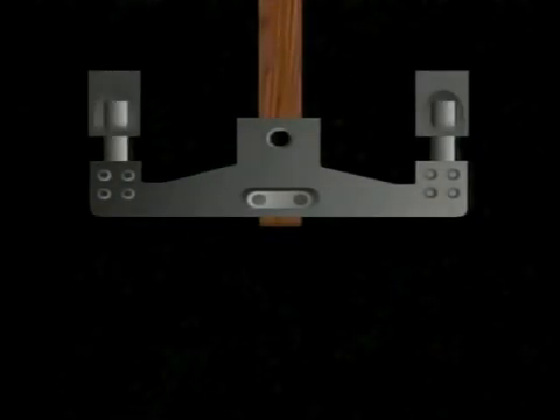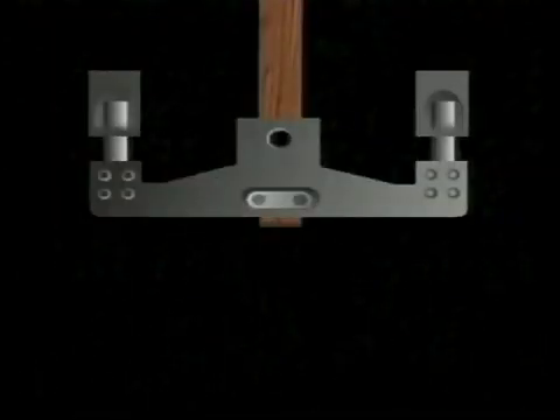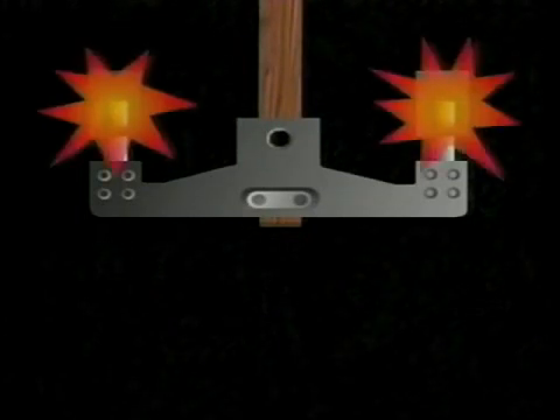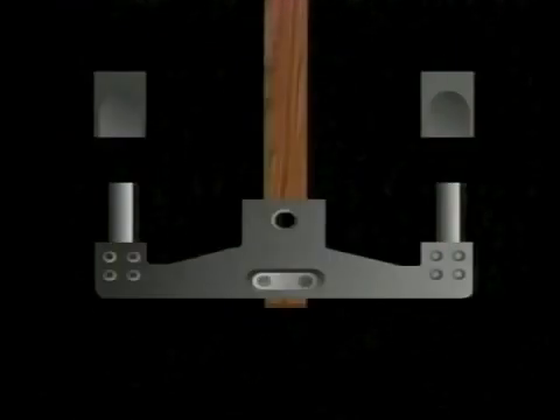thermally damaging itself. The arc interrupter of an oil-filled circuit breaker is made of an insulating material that surrounds the contacts and extinguishes the arc. When an arc is formed, the pressure created by the arc is retained inside the interrupter. As the breaker opens and the contacts separate, the moving contact passes through the interrupter.